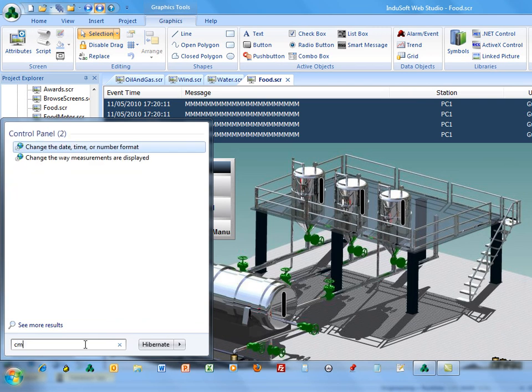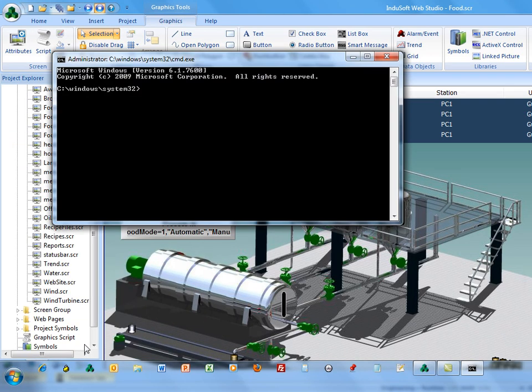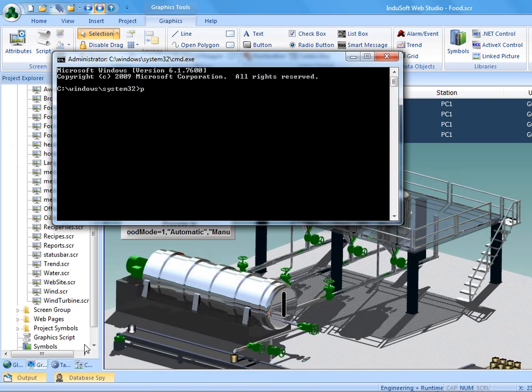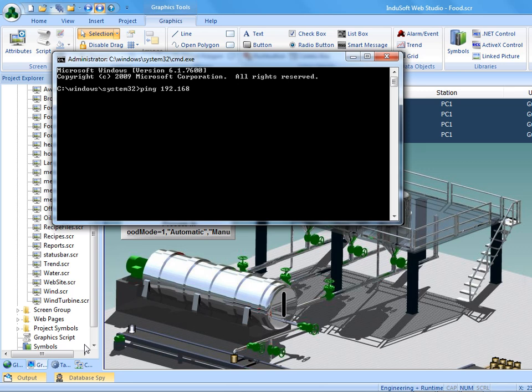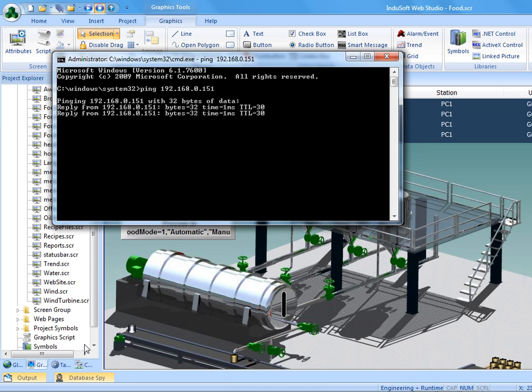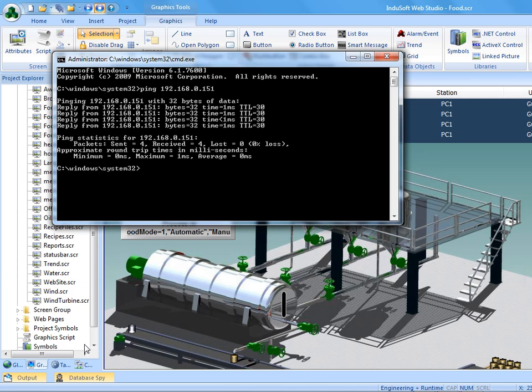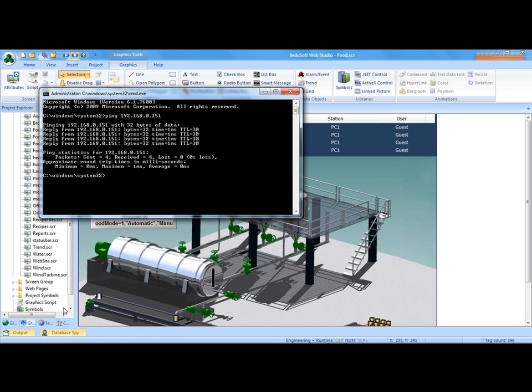We're going to ping it. So I'm going to do a CMD and ping. The PLC is at 192.168.0.151. The fact that I'm getting replies from it means that I've got the connection with the cable and the IP address and the subnet mask correct.